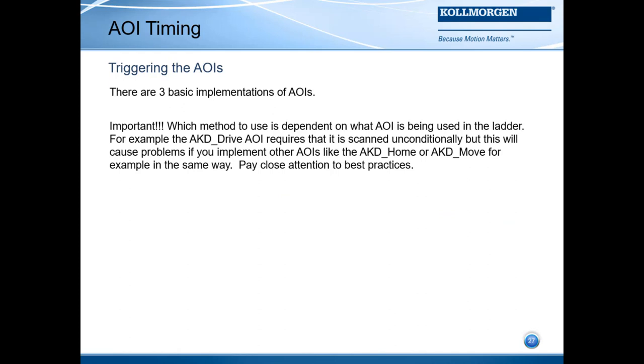It's important to note that which method to use is dependent on which add-on instruction is being used. For example, the AKD drive add-on instruction requires that it scan unconditionally, but this will cause problems if you implement other add-on instructions, like the AKD home or AKD move add-on instructions, in that same way. Pay close attention to best practices.